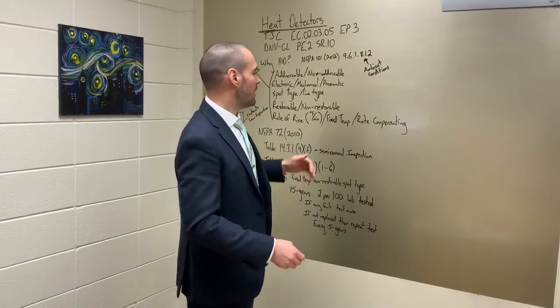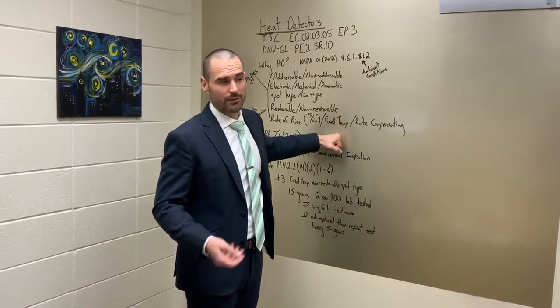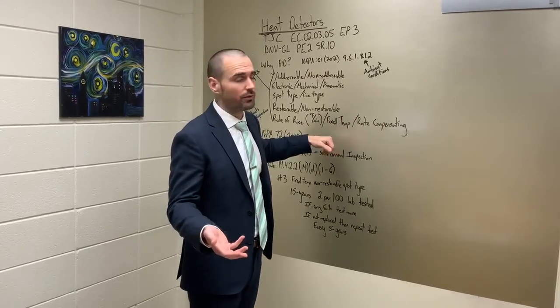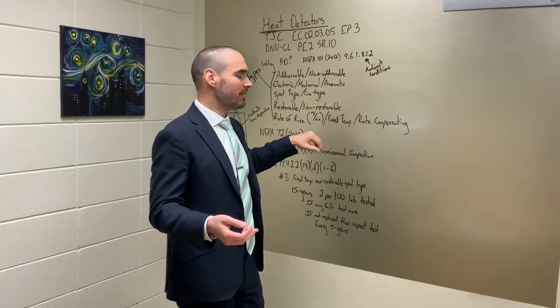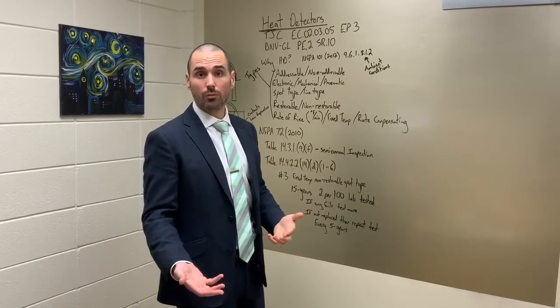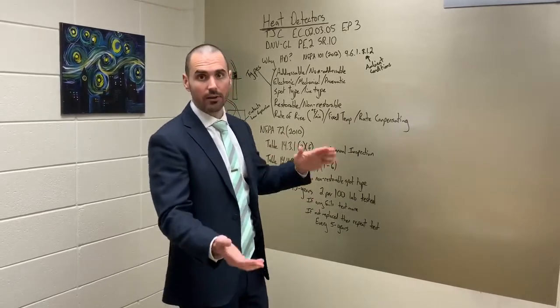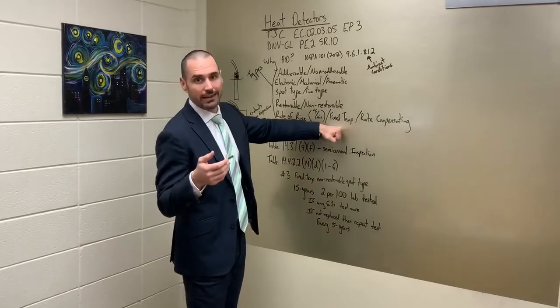Fixed temperature, it's a set temperature, typically 135. If you're in central plants, you may have a 200 degree fixed temp head, but it is just a set temperature and it doesn't go off as frequently as a rate of rise because we have thermal lag, which prevents it from going off until the ambient conditions around it are truly that temperature.